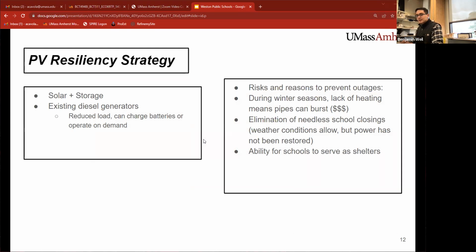These calculations show that the campus can meet the resilience goals of surviving a week-long power outage with a 1,200 kilowatt solar array, 135 kilowatt hour battery capacity, and a medium-sized 160 kilowatt generator. This size generator can generally supply one average size commercial building, but with these improvements, this one generator can actually supply power for the whole campus. So introducing the solar and storage system can reduce load on any existing diesel generators, increasing their reliability and multiplying their efficiency and efficacy.